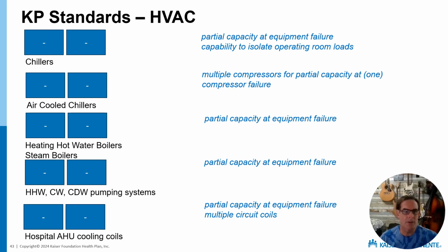Here are some of the areas where our standards require partial capacity at one equipment failure. I can't emphasize that enough. Partial capacity at one equipment failure. It's not N+1. It's partial capacity at one equipment failure. And that goes for chillers and boilers and heating hot water and steam and pumping.